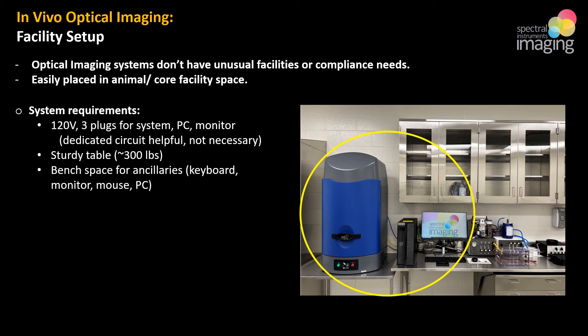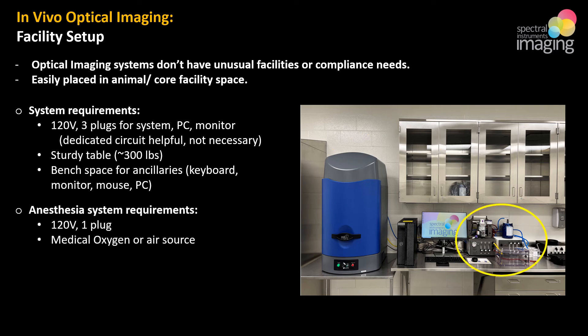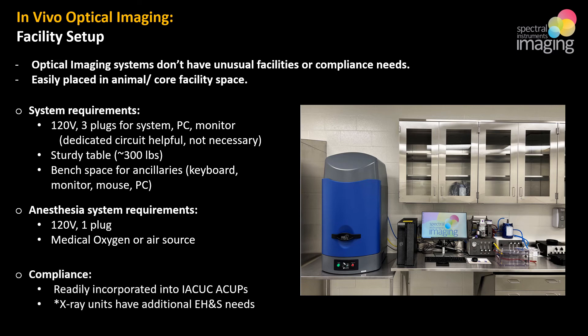Floor-standing units are about seven feet tall, so you'll want space for those. The anesthesia system needs an outlet for the vacuum pump, medical oxygen or air to drive the system, and you'll need the appropriate compliance documentation for isoflurane. These systems are readily added to animal care and use protocols. Attention is often most focused on surface sanitization between uses, which is guided by current facility protocols and manufacturer guidance for proper system safety and operation — typically not difficult hurdles.